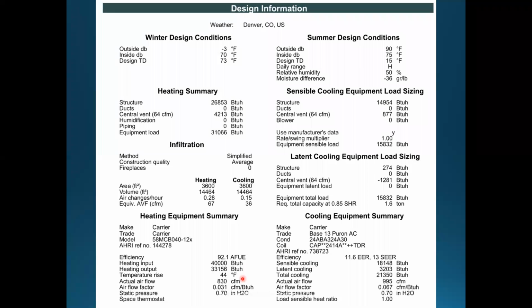Temperature rise, this is the key right here for furnaces. Gas-fired furnaces, that is the biggie. I don't care how much air you're moving. In this case, we were saying 830. I don't care what you come up with in the math here, as long as when I actually do my test in real life, my temperature rise is within the manufacturer's specifications, and it's usually a range, 15 to 45 degrees, something. That's an example. They're all different, and they're all different between models within the same manufacturer.